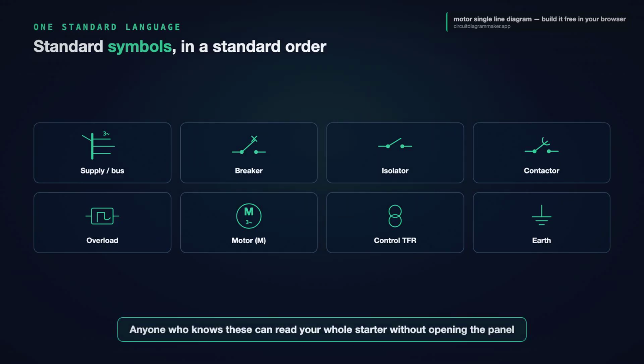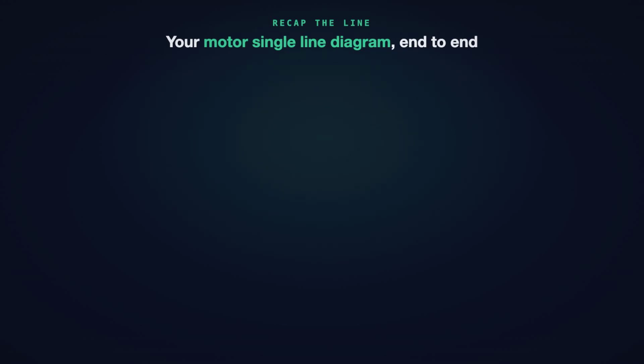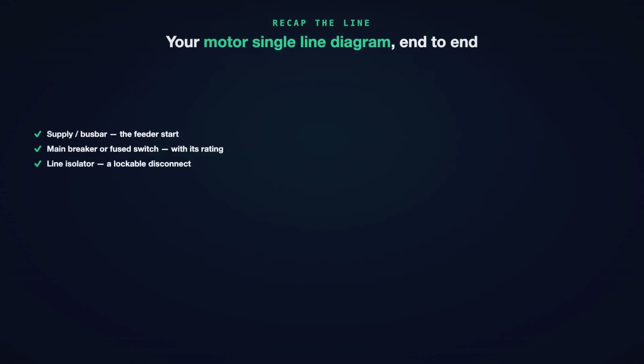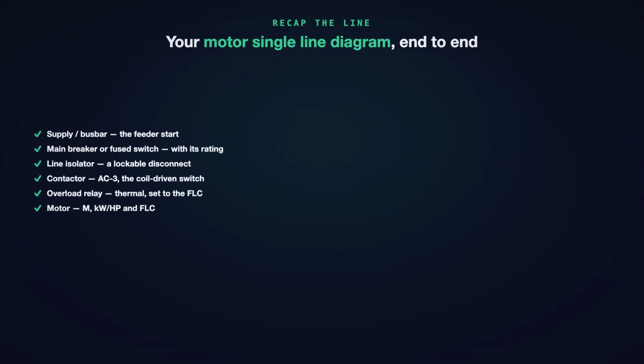That is what the panel builder works from. That is what the inspector checks. And that is what protects the people who service it later. Let us recap the line. Supply, off the bus bar. Main breaker or fuse switch with its rating. A line isolator to make it safe. The contactor, the coil-driven switch that starts the motor. The overload relay, set to the motor's full load current. The motor itself, with its kW and FLC. A control transformer tapping off to the coil. An earth bonding all of it together.